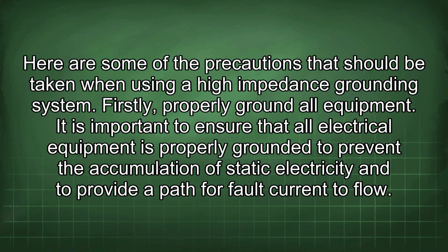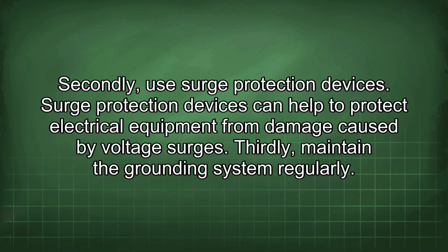Here are some of the precautions that should be taken when using a high-impedance grounding system. Firstly, properly ground all equipment. It is important to ensure that all electrical equipment is properly grounded to prevent the accumulation of static electricity and to provide a path for fault current to flow. Secondly, use surge protection devices. Surge protection devices can help to protect electrical equipment from damage caused by voltage surges.